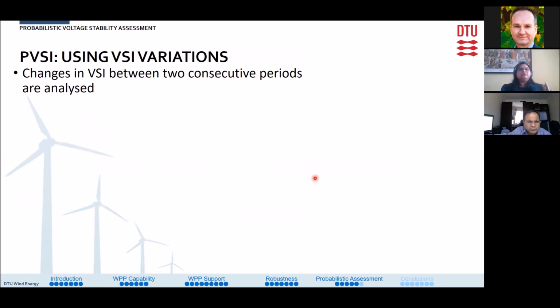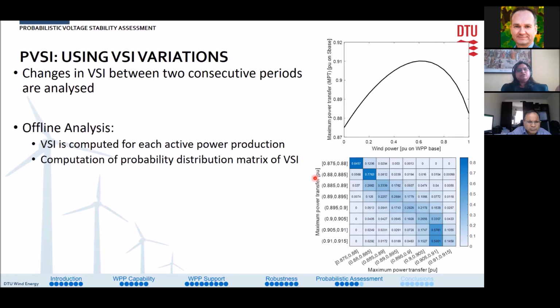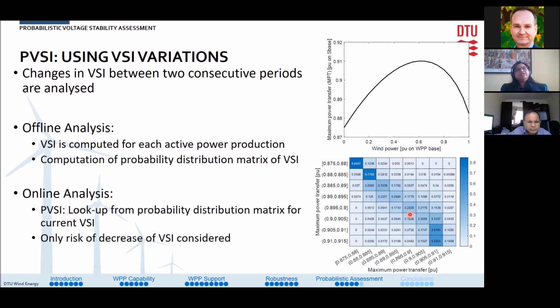The second methodology involves using variations in the voltage stability index directly. The voltage stability index varies between two consecutive time periods. In the offline phase, we calculate the voltage stability index for each active power production for a particular power system configuration, and we get a relation like the one shown in the graph. We use this relation to compute the probability distribution matrix for the voltage stability index, as shown in the figure. Then during online analysis, to calculate the probabilistic voltage stability index, we use this matrix and, based on the current value of the index, we look up the risk of a decrease in the voltage stability index, because we are more concerned about the decrease due to stress conditions.